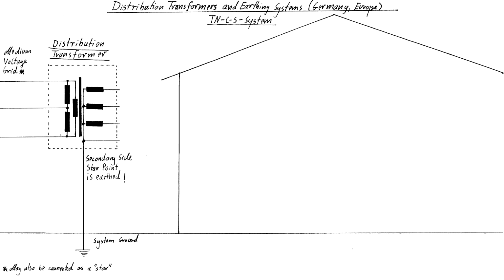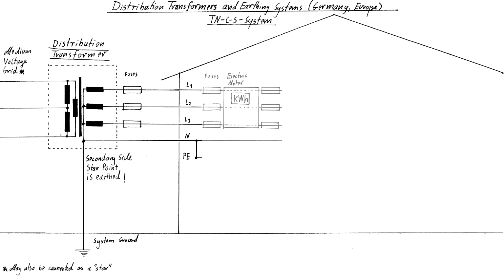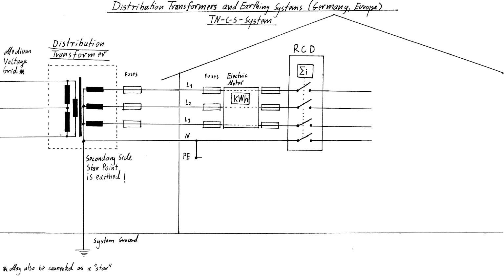From here, the three phases and a fourth conductor, called Protective Earth Neutral Conductor, abbreviated PEN, leads into the single households, where it is then split into the so-called neutral N and the protective earth conductor PE. This is just one variant of several possible earthing systems that is used in Germany and around Europe. It's called the TN-C-S system, which is short for the French words Terre neutre combinée séparée, Earth neutral combined separate, meaning that the star point is earthed, that Earth and neutral are combined and then separated inside the house. The three phases are then leading via several fuses through the electric meter, through the residual current device, and via the circuit breakers to the various single-phase and three-phase loads.